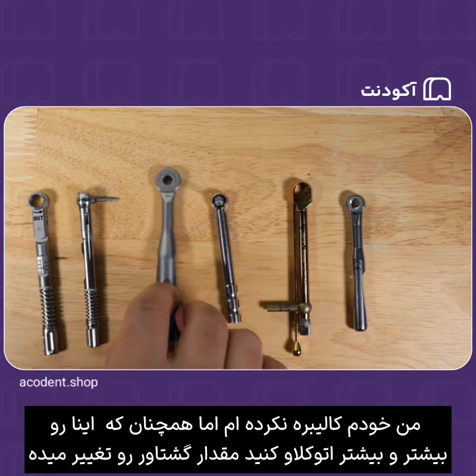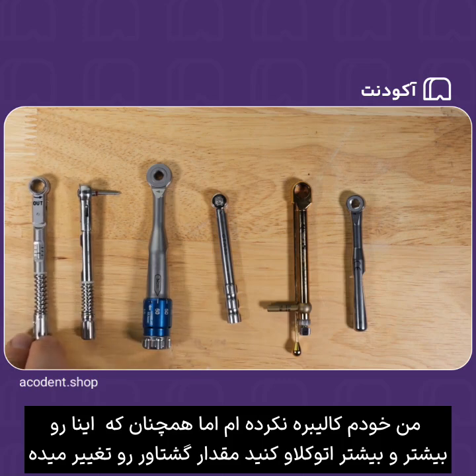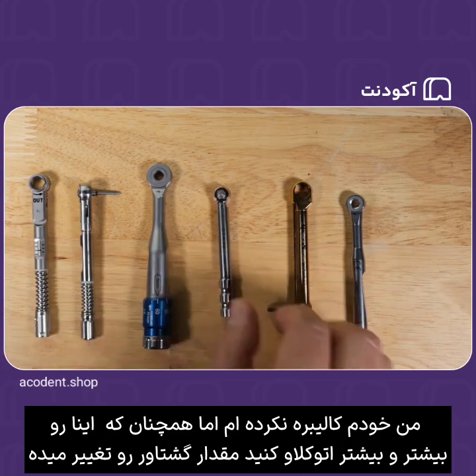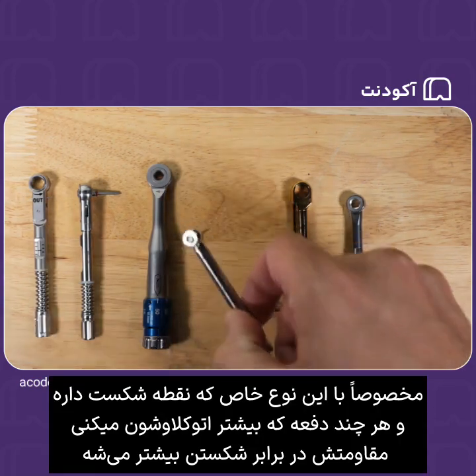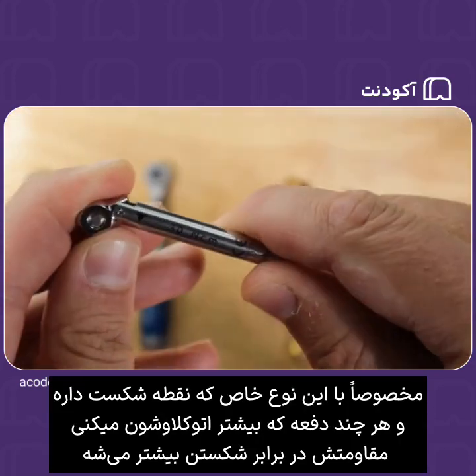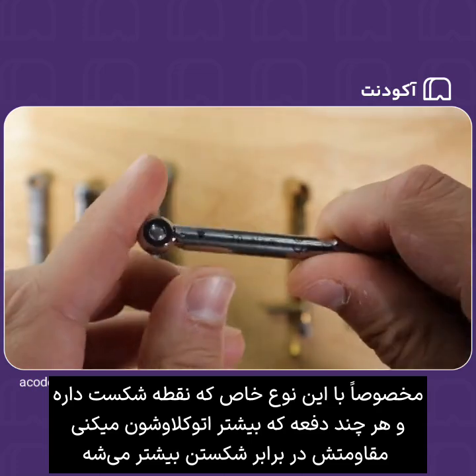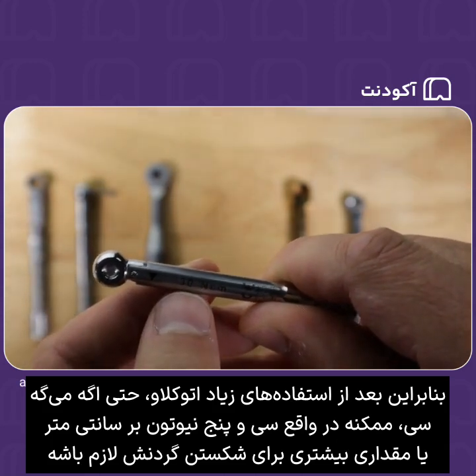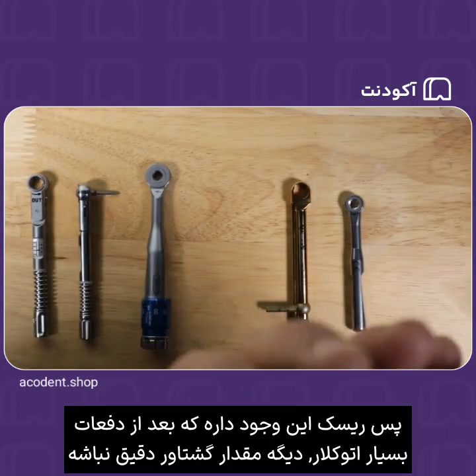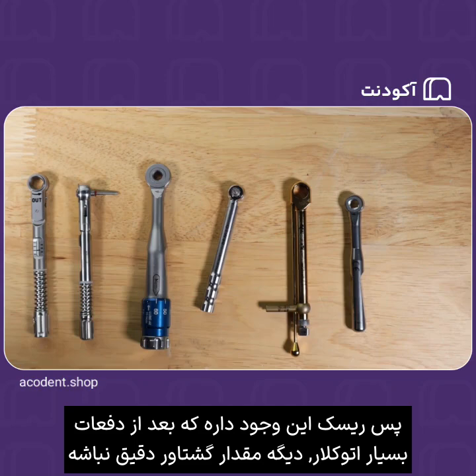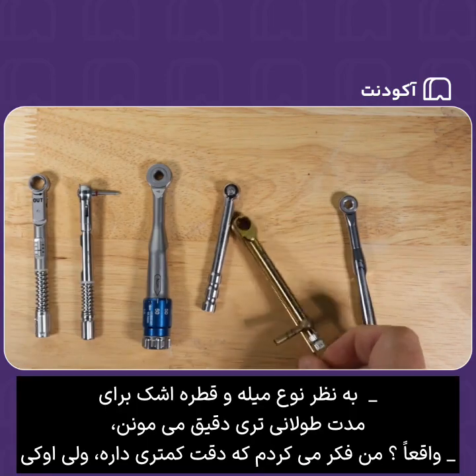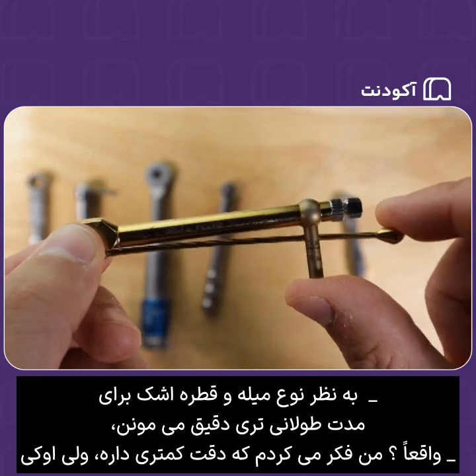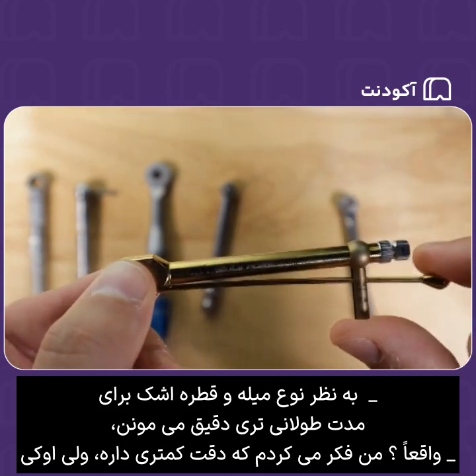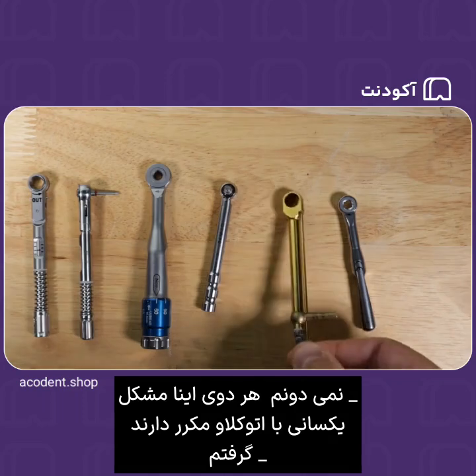Well, I haven't myself calibrated, but supposedly as you autoclave these more and more, it does change the torque value. Particularly with this particular type that has the break point, the more times you autoclave that, the more resistance there is to breaking. So after many autoclave uses, even though it says 30, it might actually take 35 or more Newton centimeters to break this neck. So the risk you run after you've autoclaved this tons of times is that the torque value might not be accurate anymore. Supposedly the bar and teardrop type stay accurate for longer. Really? I would have thought they would be less accurate, but okay. But I don't know. They both have the same issue with repeated autoclaving.